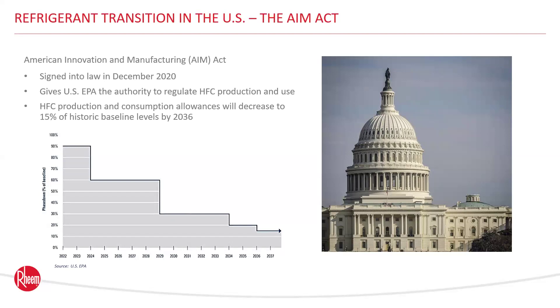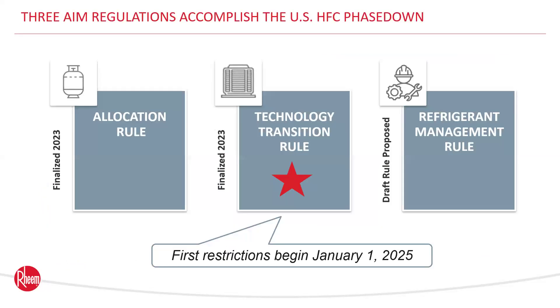The American Innovation and Manufacturing Act was signed into law in 2020 and authorizes the EPA to structure a 15-year phase-down of HFCs across a variety of applications. The AIM Act will drive production and consumption of HFCs to a mere 15% of historic baseline levels by 2036, aligning with the Kigali Amendment to the Montreal Protocol. The AIM Act directs EPA to address HFCs through: phasing down HFC production and consumption via an allowance allocation program, facilitating transitions to next-generation technologies, and maximizing reclamation while minimizing releases to the environment.